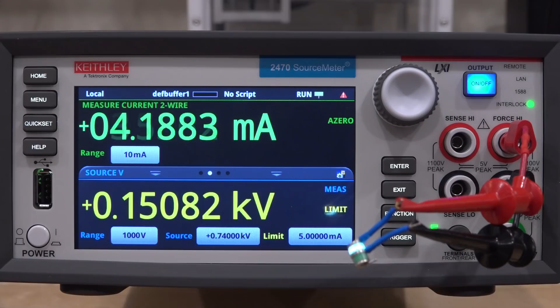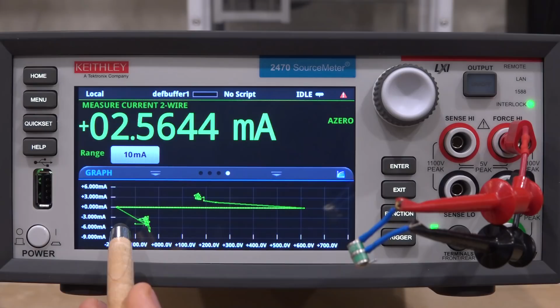Keep in mind that the instrument is trying to apply minus 500 or 600 volts, but it's only getting about 50 or 60 volts because this is already ionized. Once it drops below a certain voltage, the ionization stops. Now it's allowed to go higher and higher in voltage. And look, it's going to hit about 600, and it began again very strong, and it stopped. Let's take a look at the curve. The curve is going to look really interesting. Yeah, look at that. That is very interesting.